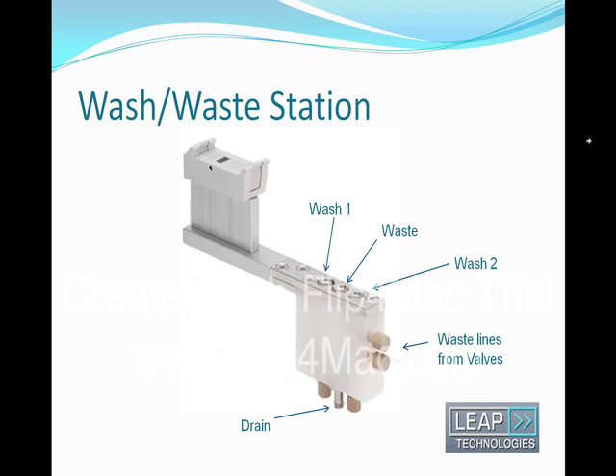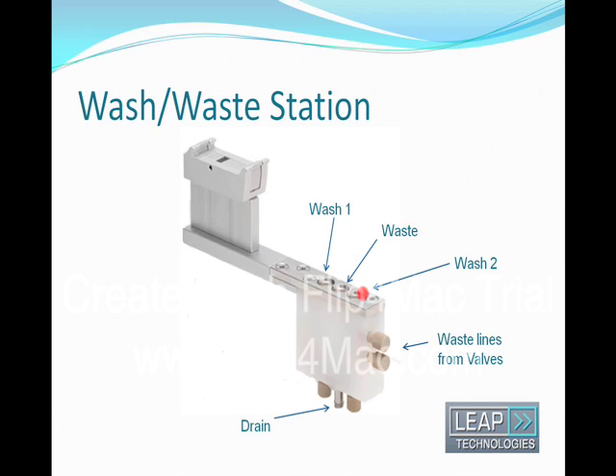This is the newly designed wash station which is passive, which means there is no independent solvent supply. Wash station one and wash station two are quite similar to the fast wash on the conventional PAL with the exception that the solvent is coming from the pumps through the syringe needle. The outside and the inside of the needle are washed by this flow.